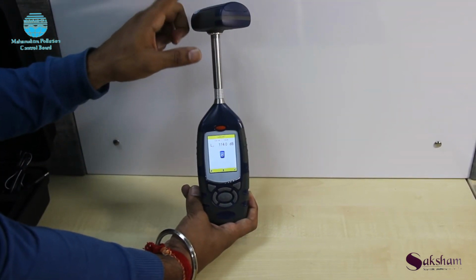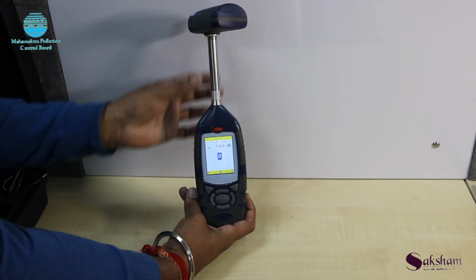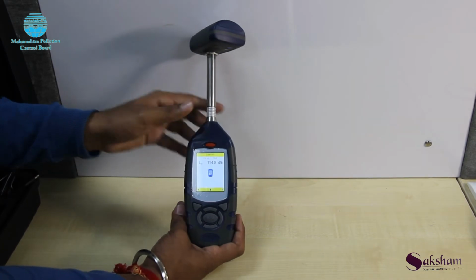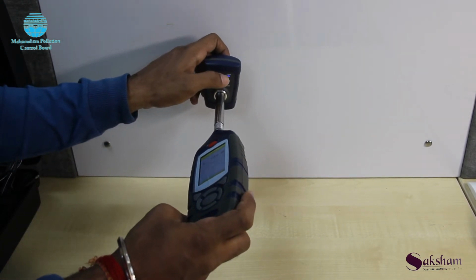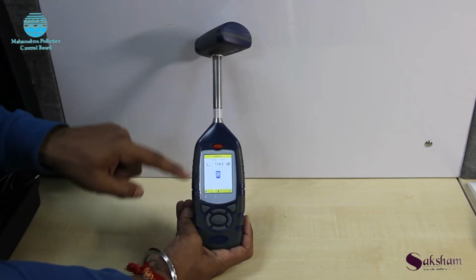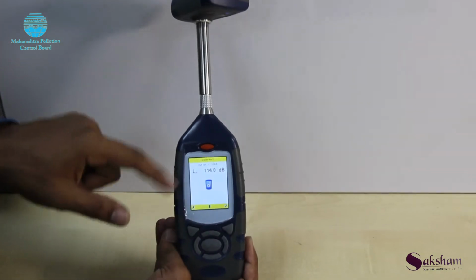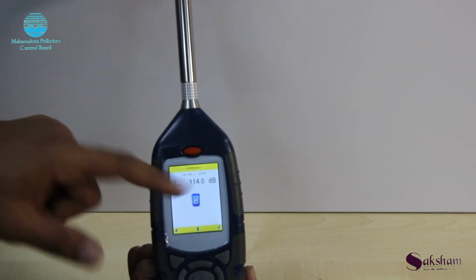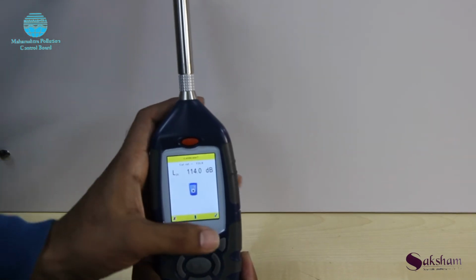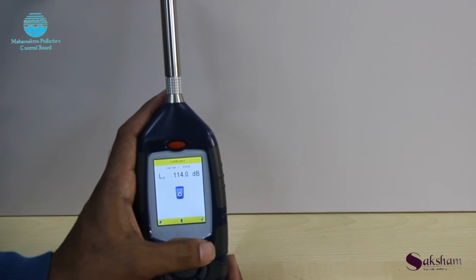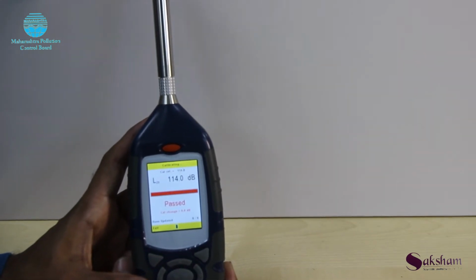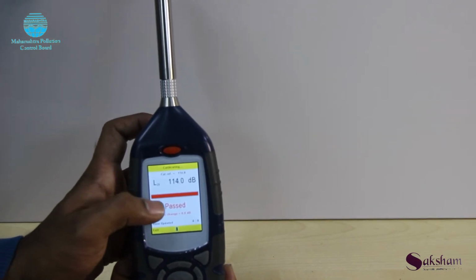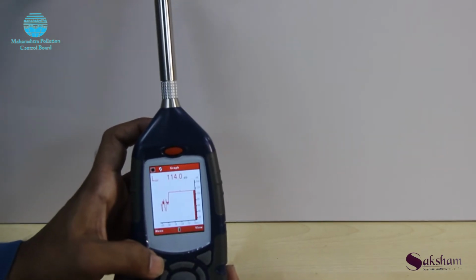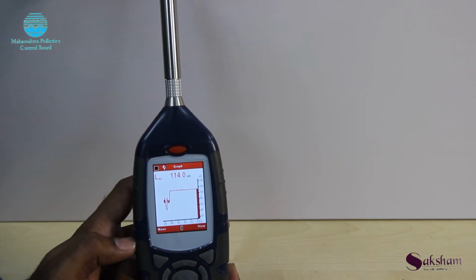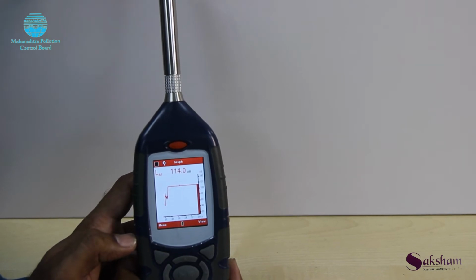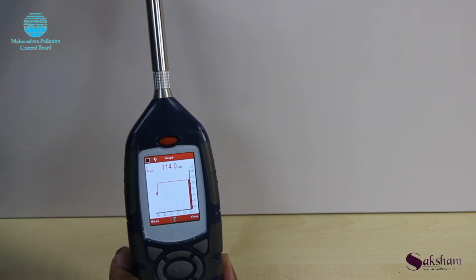I will plug this acoustic calibrator above the microphone. As soon as I plug it in, this 114 blinking light becomes stable, and this red colored home screen changes into the yellow colored screen. Now it is showing "Calibrate?", meaning to do the calibration I just need to press this right colored mark, so it will automatically calibrate and show the result as passed. In this way, every time you use your sound level meter kit for taking a reading, we do the calibration first in the same way.